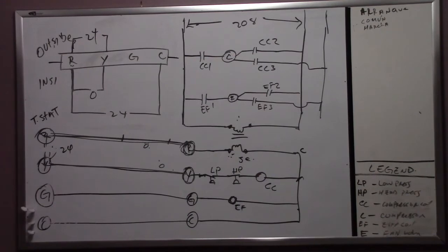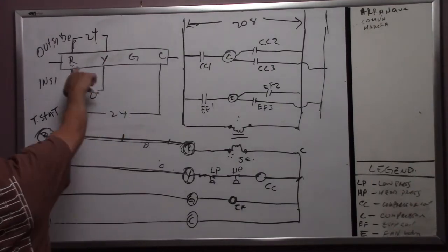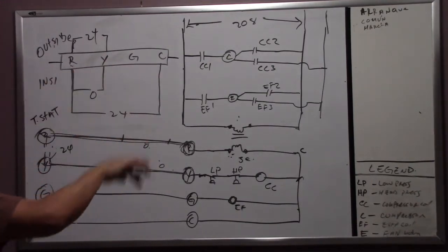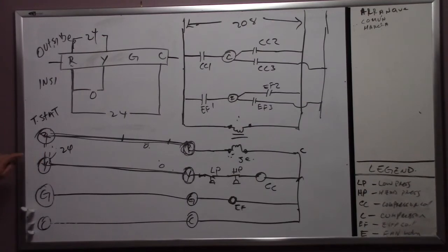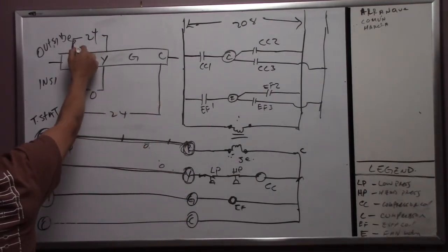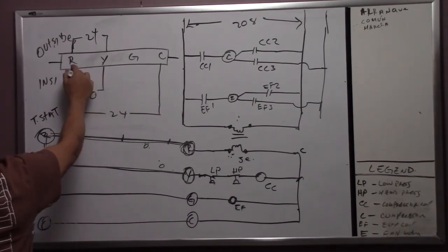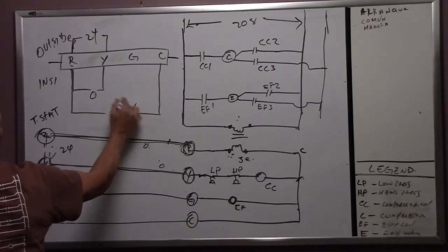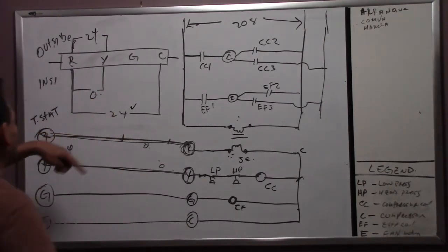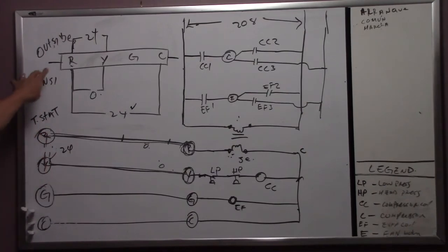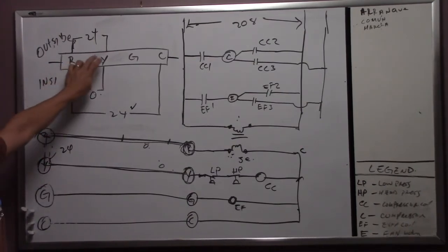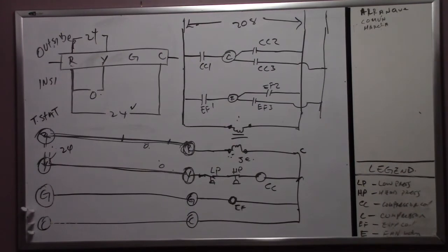There are a couple of safeties outside the air conditioner. You have a high level float switch, you have a remote shutdown, and you probably have a pressure control or something else. Oh no, my correction. Remote shutdown is between R and C, but we're going to talk about it later on. What I'm trying to say is that between R and Y you get 0, and between R and C you get 24 volts, then the problem is inside the air conditioner. And same thing, if you check between R and Y and you get 24 volts, that's the problem outside. Okay.